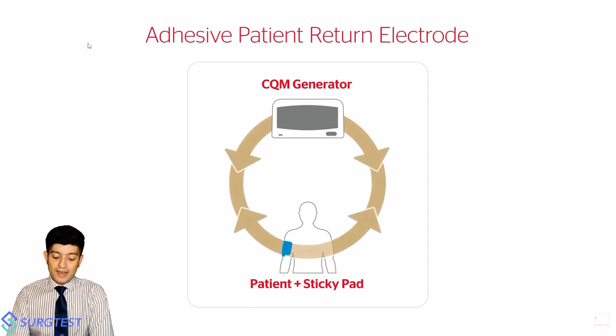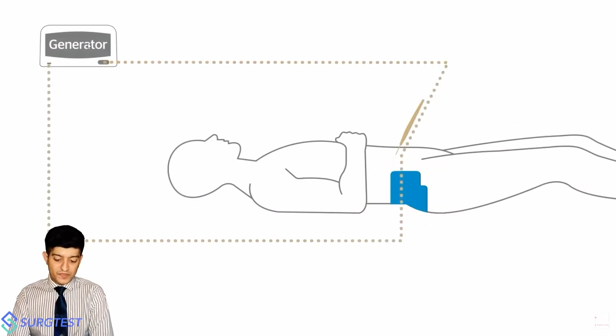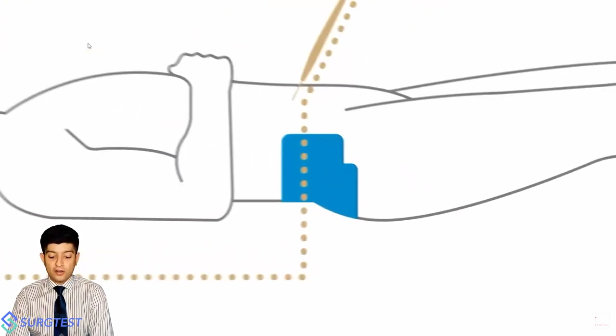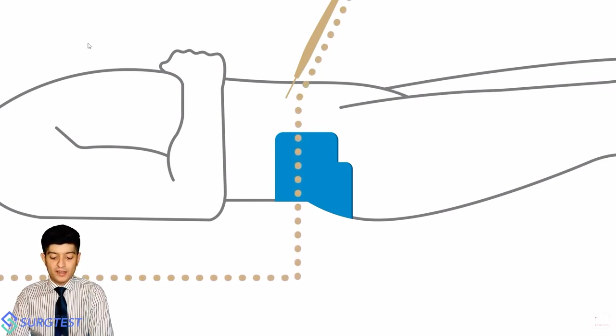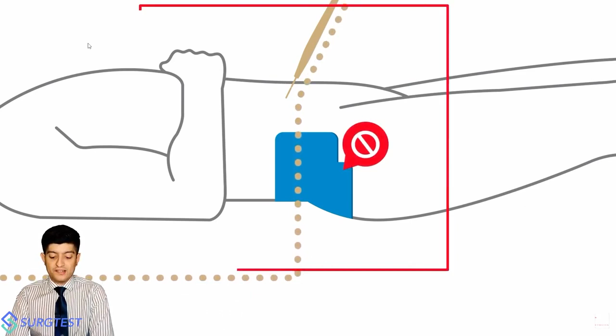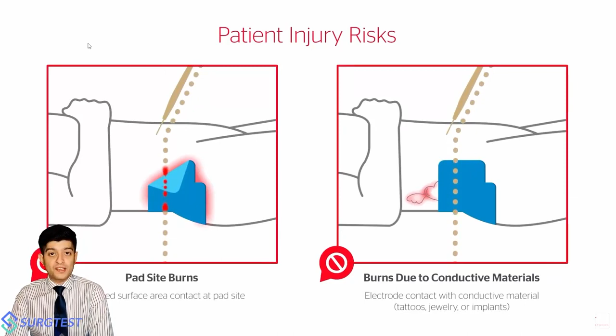So in most situations, you have an isolated circuit that is generated between the ESU and the patient, and the dispersive electrode is applied with the help of an adhesive pad. You can see the entire circuit on screen has been completed, and there is flow of electrons all across the patient, from one end, that's one pole, that's a cautery pen, to the other end, which is the dispersive electrode. If you have problems at the dispersive electrode, such as a poor attachment, or surrounding areas like tattoos and implants that have low resistance, the current preferentially flows through those areas, and that is a recipe for setting up burns.